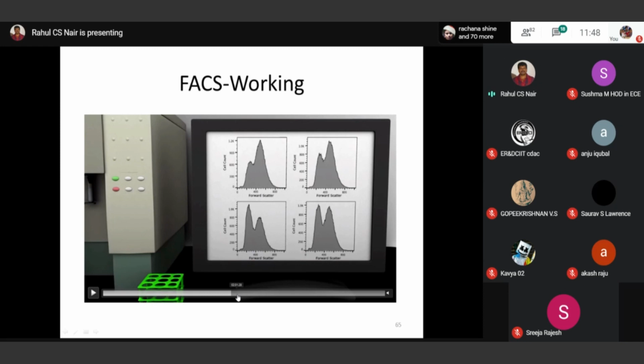Now there is another scattering, that is side scattering. The side scattering depends on the internal complexity of the cell. The cells contain various shapes, different forward scatter, different cell sizes, right? Similarly, in the case of side scatter... depending on the forward scattered light, this detector will produce peaks accordingly, depending on the size. So it can be plotted with the forward scatter information on the x-axis and cell count on the y-axis. And this is the diagram that is typically obtained from a FACS machine. And you can also study the side scatter.